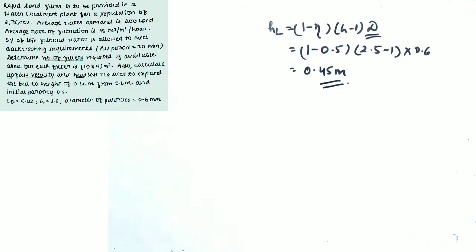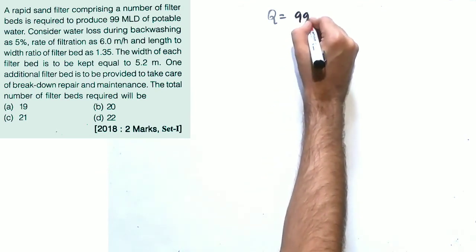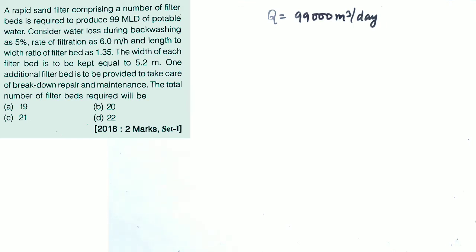I hope you are clear with this portion. Now there is one more question related to rapid sand filter — the GATE 2018 question — which will sound easy after solving the extensive one. A rapid sand filter is required to produce 99 MLD of potable water. Backwashing loss is 5%, rate of filtration is 6 m/hr, length-to-width ratio is 1.35, and width is given as 5.2 m. You are asked to calculate the total number of filters, including one standby filter. The discharge here is already the design discharge: 99,000 m³/day.